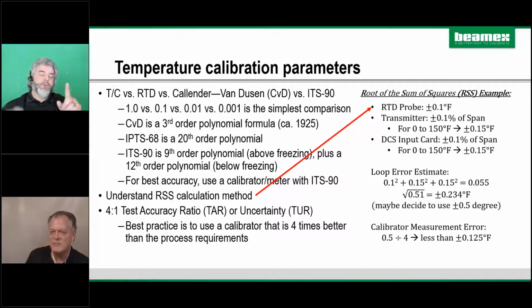Does that make sense? So what you've done is answer one of the questions that we get all the time, which is: I have this thing, what should I use as a calibration tolerance? And you worked from the end and went back to the beginning. What's the accuracy of each individual item, whether it's one transmitter or a loop? And once you have that number, you divide it by 4 to determine how accurate your standard should be. Your standard should be 4 times more accurate than what you're trying to measure.